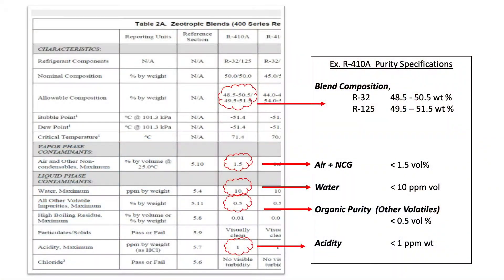So I want to put one up here for example — R410a, a very common refrigerant — and we can see the types of things that are considered as far as the purity specification. There's overall purity, organic purity of the refrigerant itself, air and non-condensables, moisture, non-volatile residue, acid, and some other things.